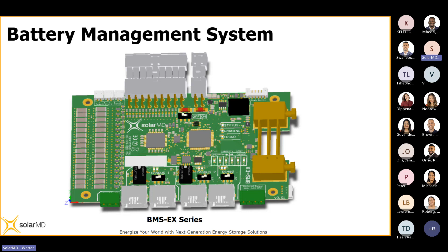Here's the slide with most of what I've described. Looking at the LED indicators on the left-hand side of the BMS, there's a status light on the top left, which should generally be green. The warning light illuminates orange if there's a problem - saying the BMS isn't happy about the state of something. This could be a cell that's too high or too low, one of the batteries missing from the cluster, or a loss in communication with the inverter.